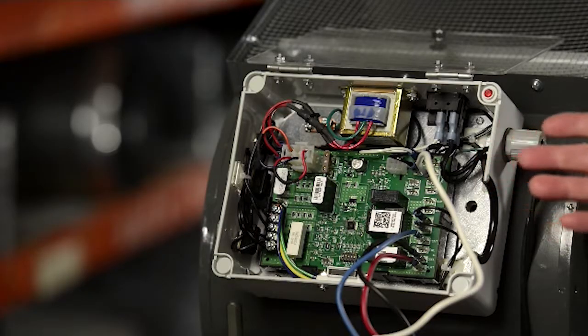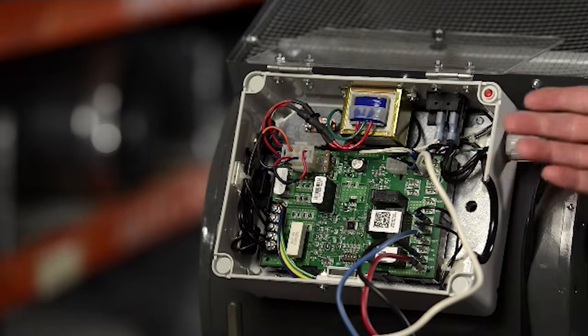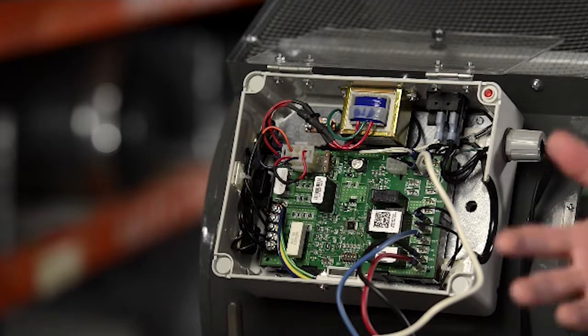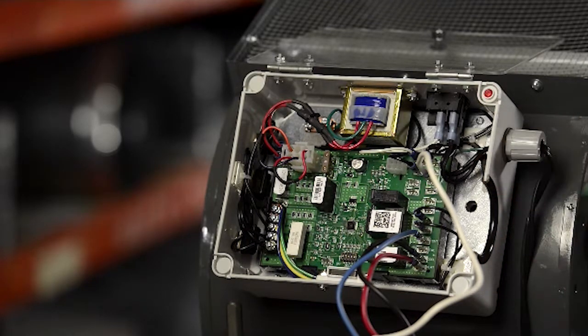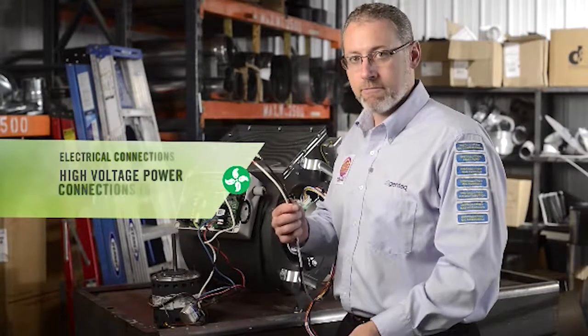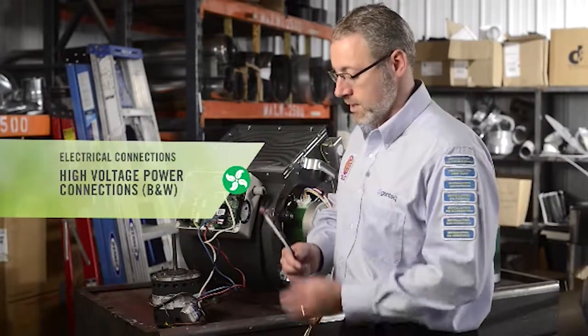So this could be any HVAC system with a PSC motor. It could be heating only, heating and cooling. This one happens to be a heating and cooling system, and it happens to have a circuit board. You can connect the Evergreen IM to systems that do not have circuit boards and simply have fan relays, but we're going to go through it here on the circuit board. I'm going to start with the high voltage power connections. That's the black and white connections.